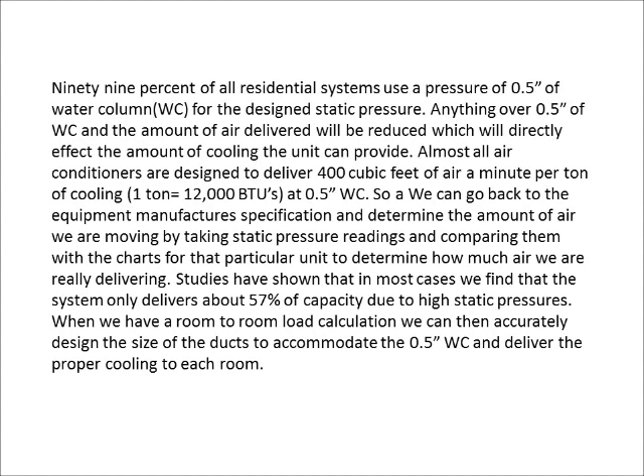The amount of air delivered will be reduced, which directly affects the amount of cooling the unit can provide. Almost all air conditioners are designed to deliver 400 cubic feet of air per minute per ton of cooling. A ton of cooling equals 12,000 BTUs. For example, if we have 3 tons of cooling — 36,000 BTUs — that would require 1,200 CFM (3 × 400). We can then check the equipment manufacturer specifications, take static pressure readings, and compare them with charts for the particular unit to determine how much air we're really delivering. Studies have shown that in most cases, systems only deliver about 57% of capacity due to high static pressures. With a room-to-room load calculation, we can accurately design and size the ducts to accommodate 0.5 inches of water column and deliver proper cooling to each room.